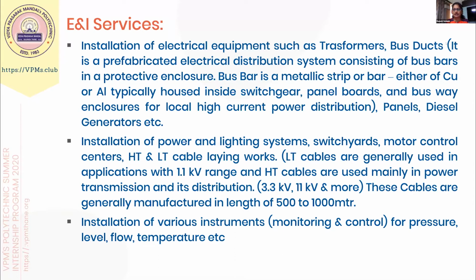Then installation of power and lighting systems, switch yards, motor control centers, HT and LT cable laying works. So HT is high tension cable laying, which is used mainly in power transmission and distribution. And LT is generally used in applications where the voltage level is low, up to 1.1 kV. Beyond 1.1 kV, the HT cables are used. The ratings are like 3.3 kV or 11 kV and more than that also. Cables are generally manufactured in lengths of 500 to 1000 meters. So this is one type of work.